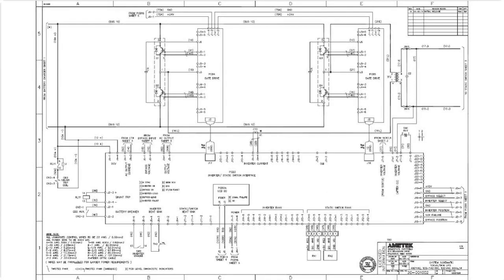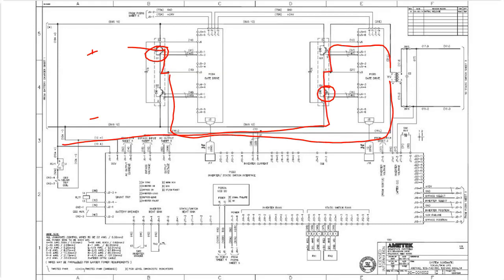And then this is the inverter drawing, okay? So we've got our positive at the top there and our negative coming in. Then it goes into our inverter H bridge. Basically, we turn the IGBTs on, which is an insulated gate bipolar transistor. It's our power switch of choice, and the power flow will be through that transistor out to our transformer here, and then the negative will return down through there and back down to our negative. So that will give us our negative going, because remember this is more positive than that. That gives us a negative pulse of PWM, because this is a PWM machine, which is pulse width modulation.